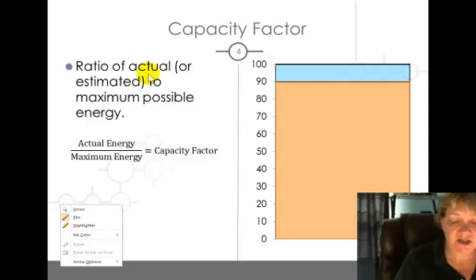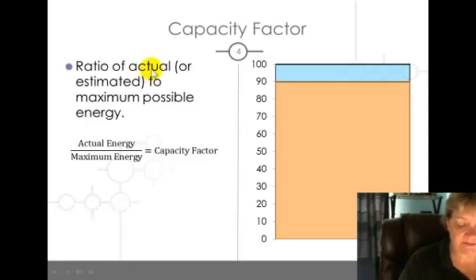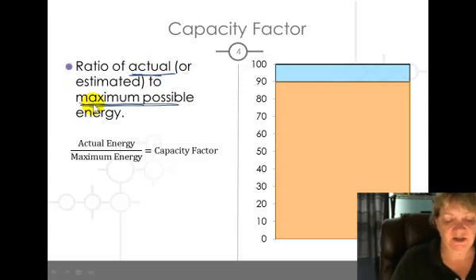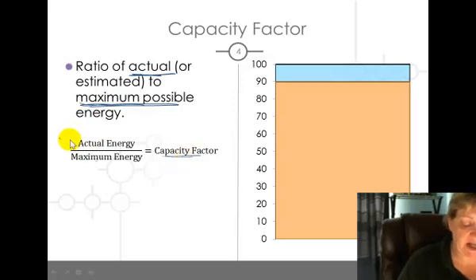So what's capacity factor? It's really simple. It's simply a ratio of the actual or estimated to the maximum possible energy. So actual over maximum equals capacity factor. Since both of these are, you want to make sure they're in watt hours or watt days. When you divide one into the other, you get this, and usually we express it as a percent, so I multiply the answer by a hundred.